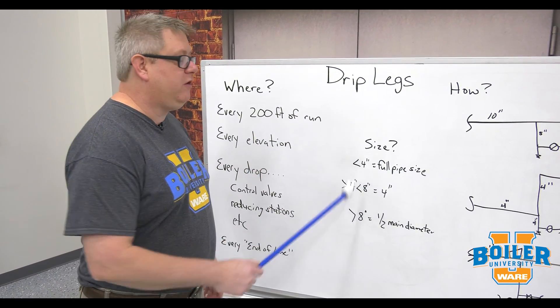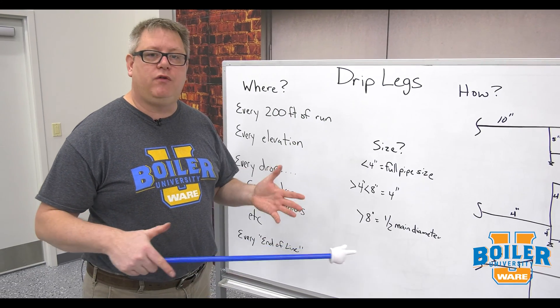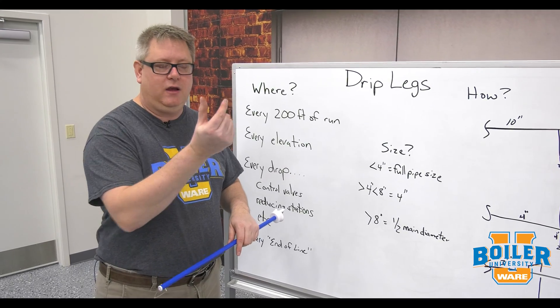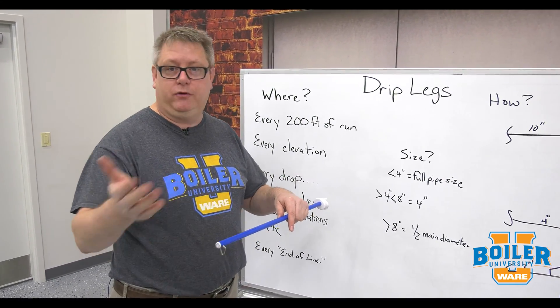Anything under 4 inches, we want to do a full-size drip leg. Over and over again I will see a 3/4-inch weld-a-let in the bottom of a 4-inch pipe that's supposed to be a drip leg.